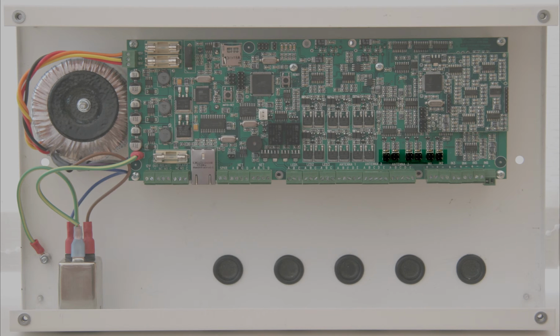Above the antenna connections are the jumpers that select the routing for the incoming signal. If the jumpers are positioned on the left hand side of the contacts, the incoming signals are coming in from the antennas. If the jumpers are fitted to the right hand side, the inputs are coming in from the auxiliary input terminals. At the bottom right of the circuit board you can see the auxiliary inputs which we use for specialist antennas such as door guard antennas and in some cases floor guard antennas.